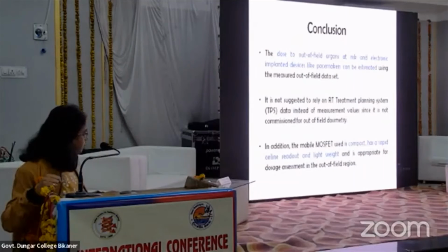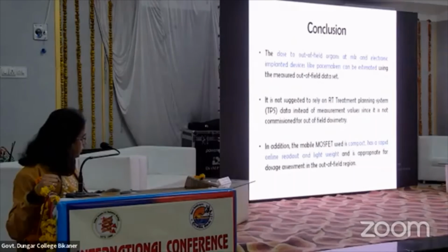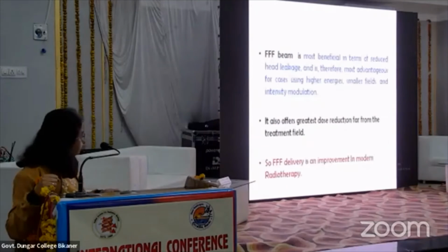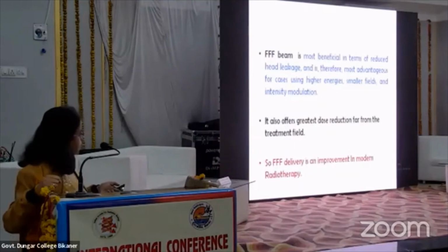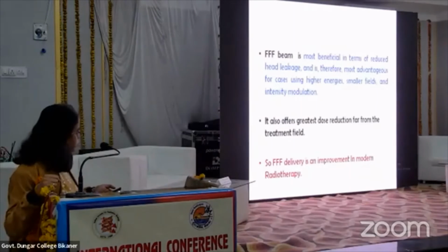In addition, the MOSFET used is compact, and it has a rapid online readout and is lightweight, and it is appropriate for dose assessment in the out of field region. So the triple F beam is most beneficial in terms of reduced head leakage, and is therefore most advantageous for cases using higher energies, smaller fields, and intensity modulation. And it also offers the greatest dose reduction far from the treatment field.